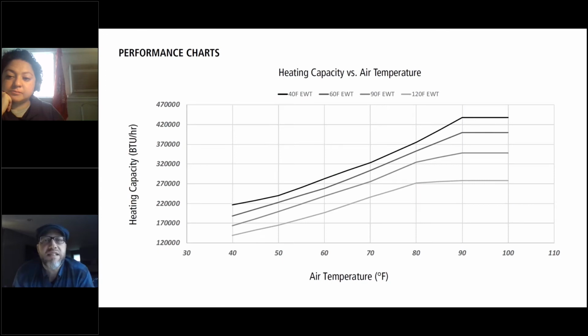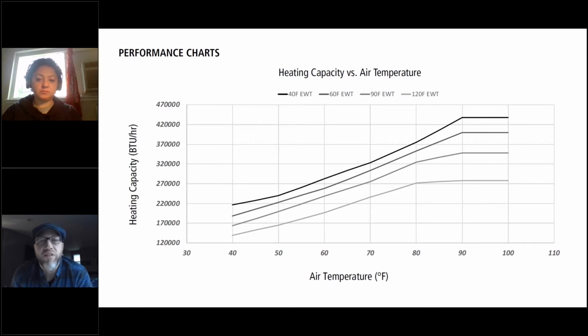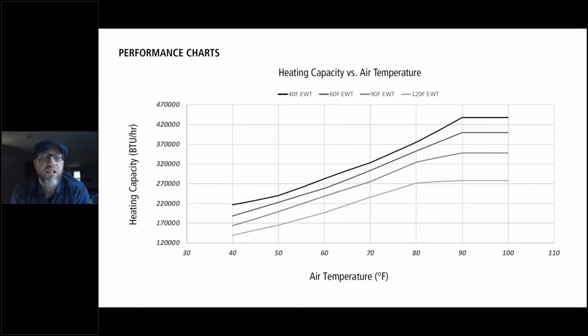And here's an example of why you want to do that. This is a performance chart for a Nyle and A.O. Smith heat pump. If you look at the curve, you can see the bottom curve shows the air temperature, so that's the entering air entering the evaporator, which is the part of the heat pump that sucks the heat out of the air. The heat capacity is shown on the left. If you look at the 4 different curves, we've got 40, 60, 90, and 120 entering water temp. And you can see that if your return water temperature is really cold, you're going to get a lot of capacity.